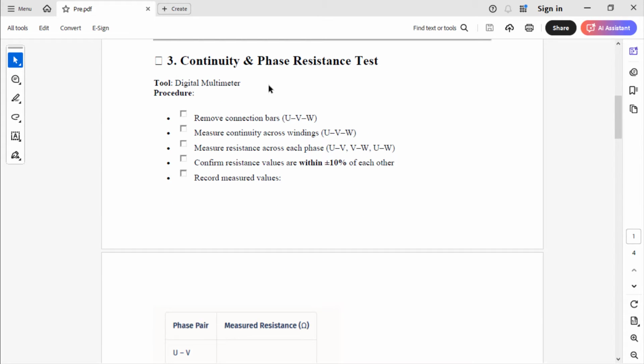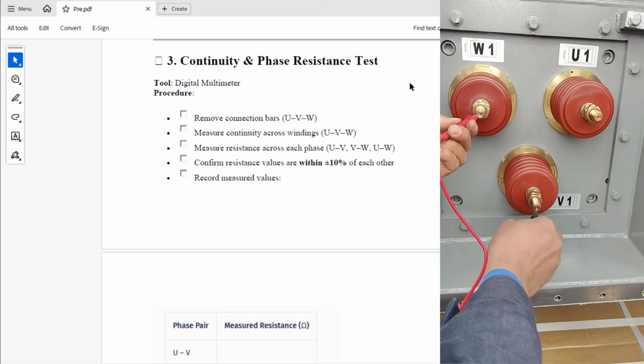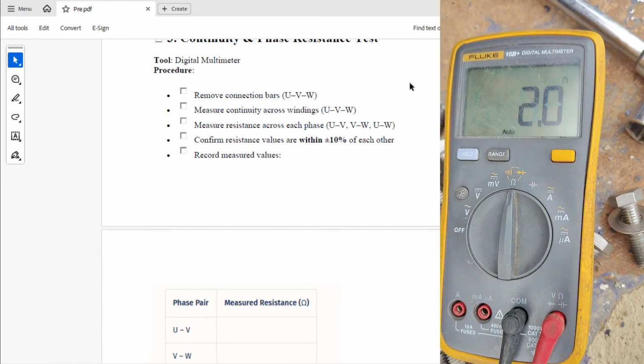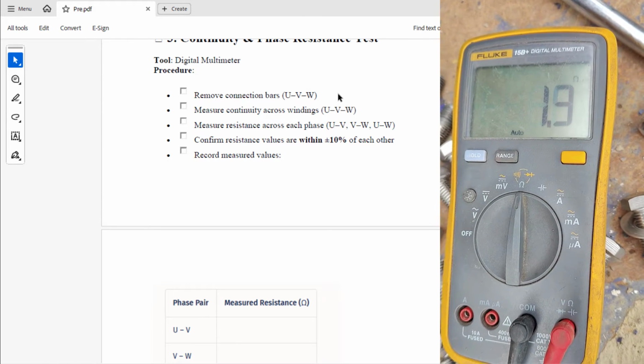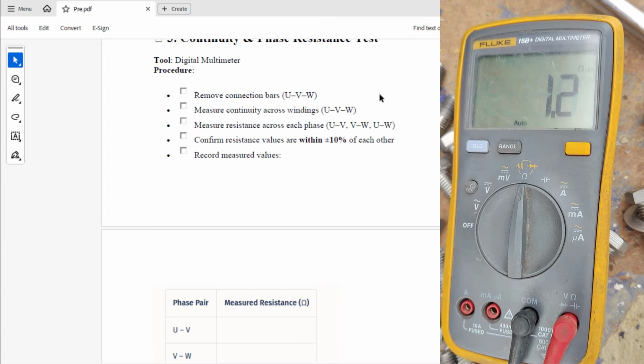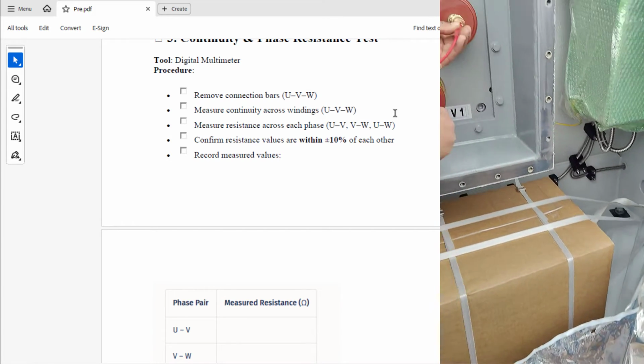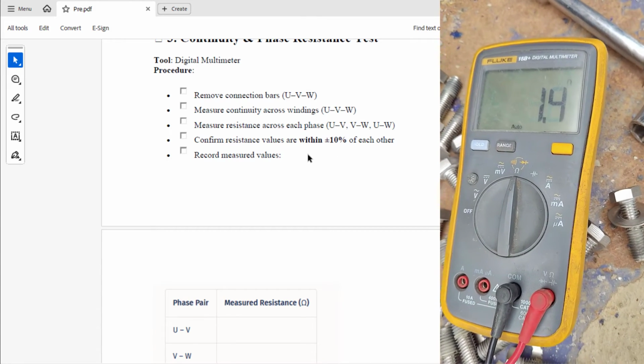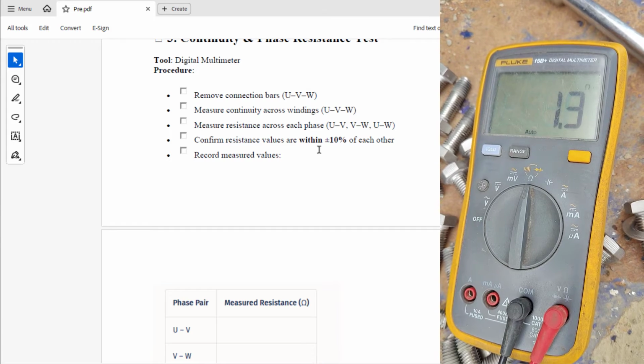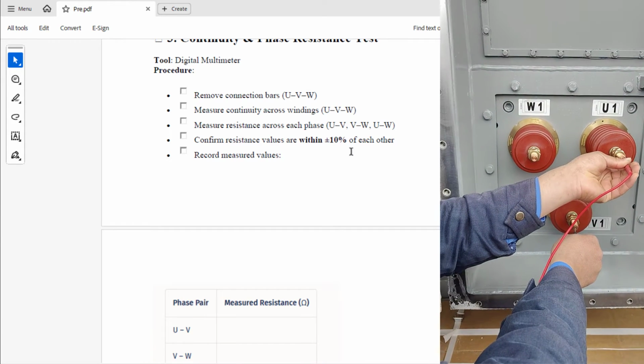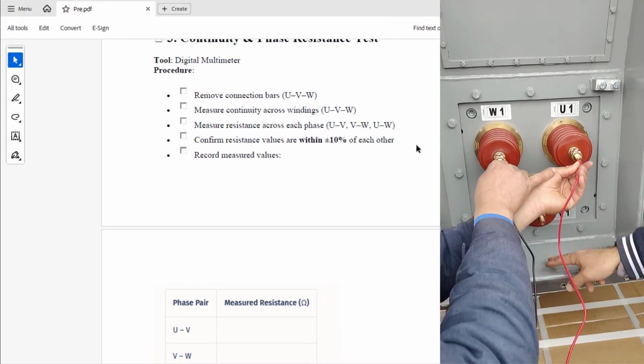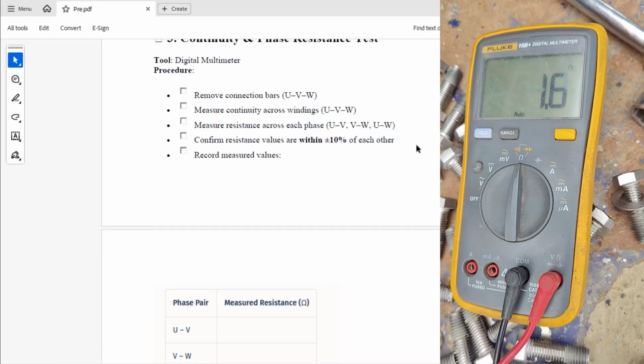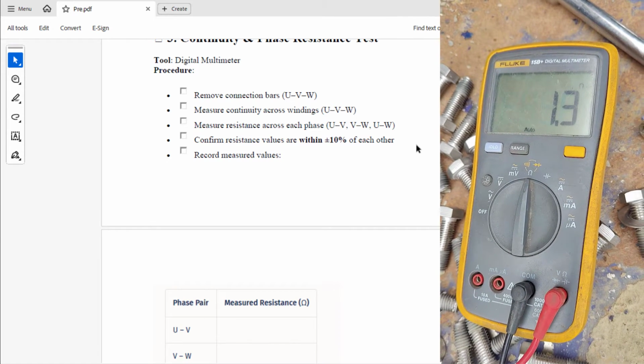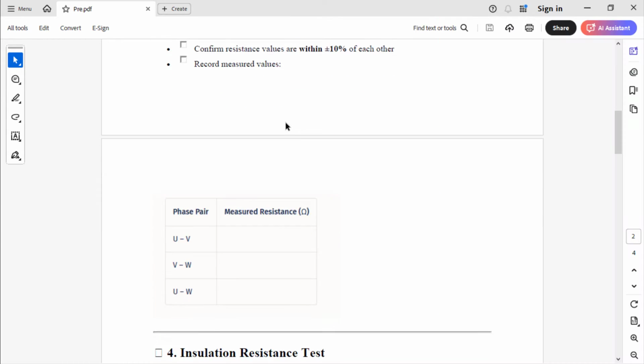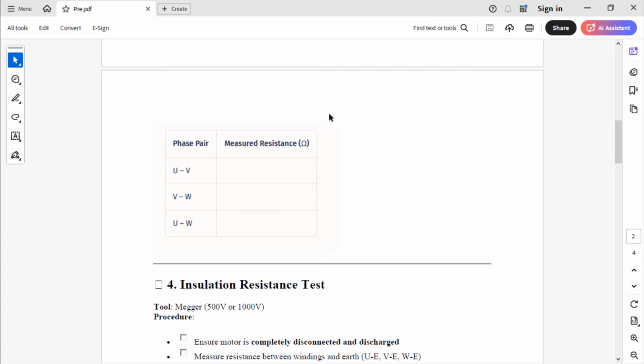Now let's start making a test. It's a continuity or phase resistance test, or we also call it a winding resistance test. We use a digital multimeter or avometer. We remove the connection bars U, V, W so that every single winding is alone. Now we will measure continuity across windings U, V, W and we measure resistance. We record every single resistance value between UV, VW and UW and confirm resistance values are within plus or minus 10% of each other. It must be balanced, it must be equal. And we record measured values to compare them with our fingerprint values.